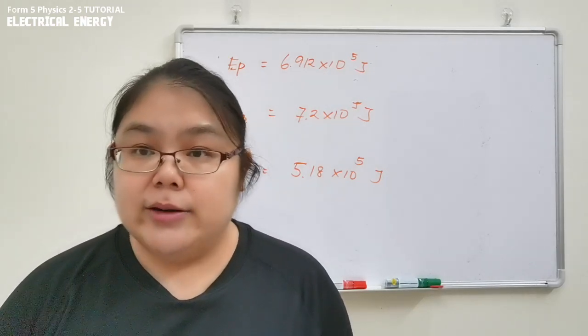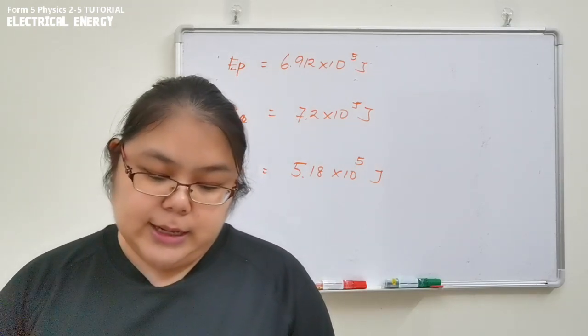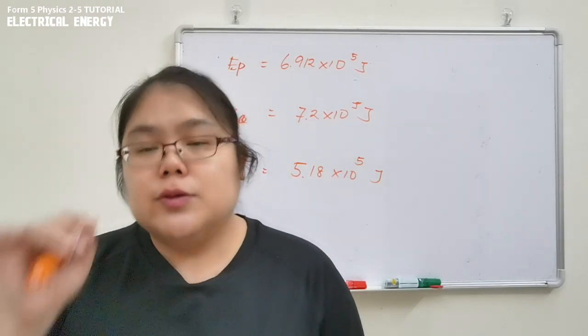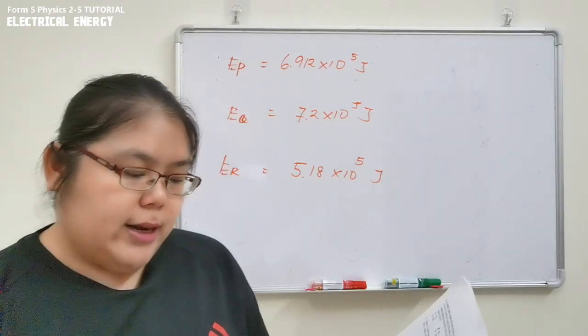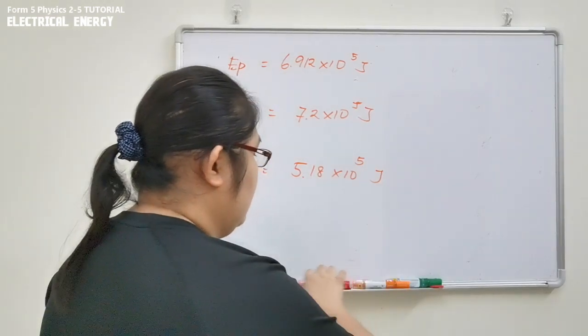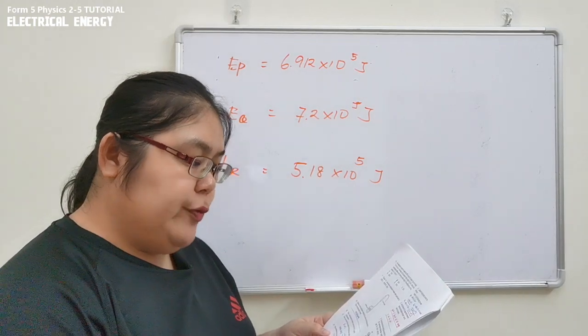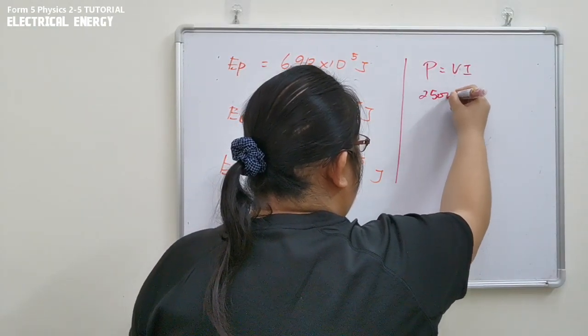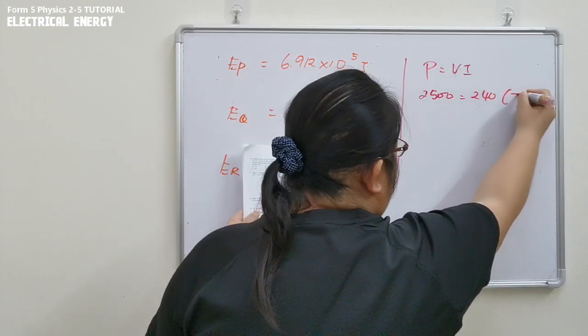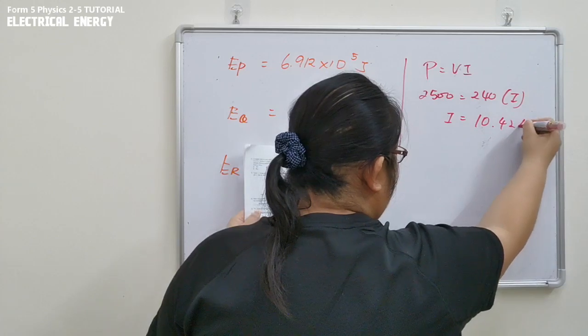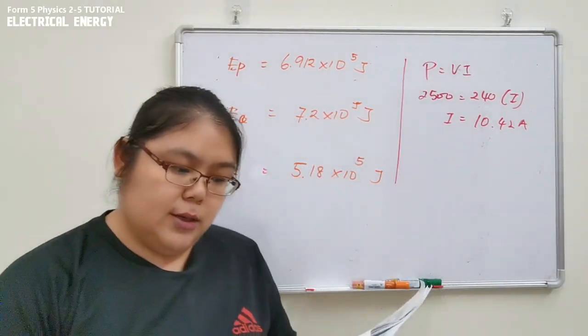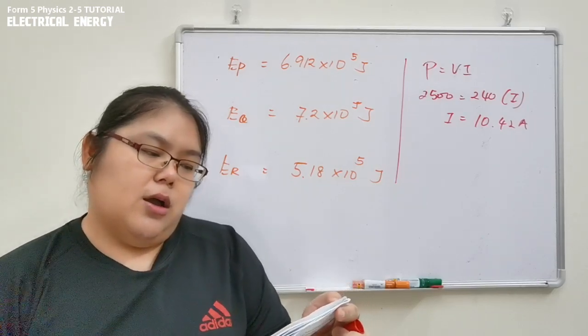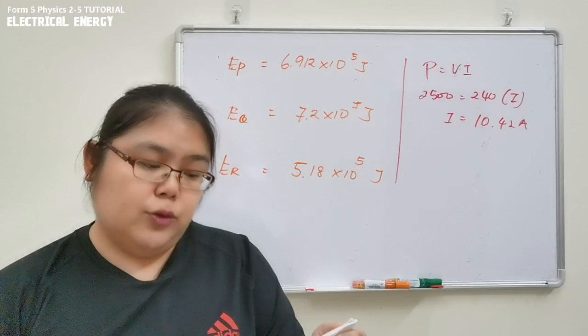For part (a), using P = VI with P = 2500 W and V = 240 V, the current is 10.42 amperes. This is the current flowing through the cable. For part (b), referring to the table, we need to choose the smallest wire diameter that can safely support more than 10.42 amperes.